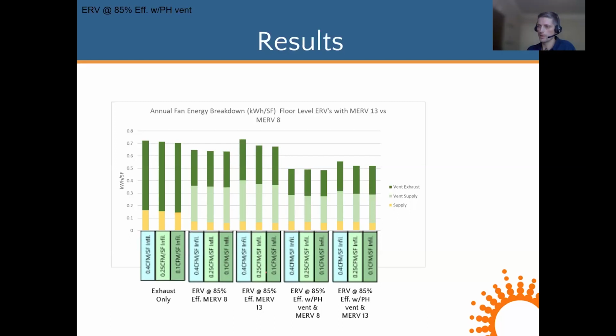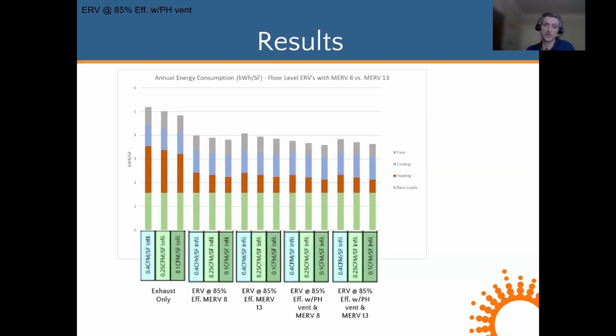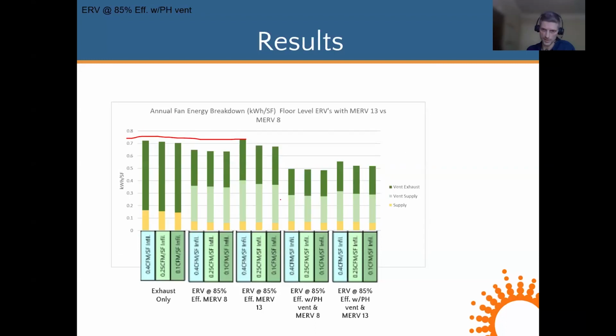So the 85% effective ERV here with the lowest kind of code level infiltration, that ends up with a fan power consumption that's a little bit more than the exhaust only strategy, but every other scenario still has lower fan power and much lower total energy consumption. So that was good to see. But this analysis only looked at floor level ERVs. Floor level ERVs are the preferred approach because we have lower static pressure, but often we see ERVs in rooftop scenario, and that has a lot more ductwork to a lot higher static pressure to overcome. So we also wanted to compare rooftop ERVs with rooftop exhaust only scenario.